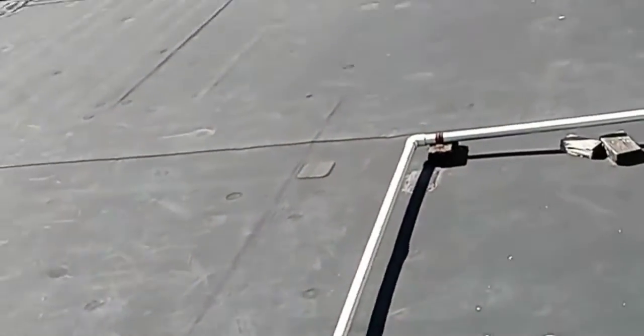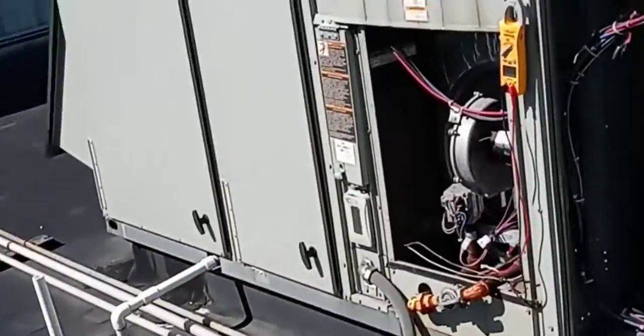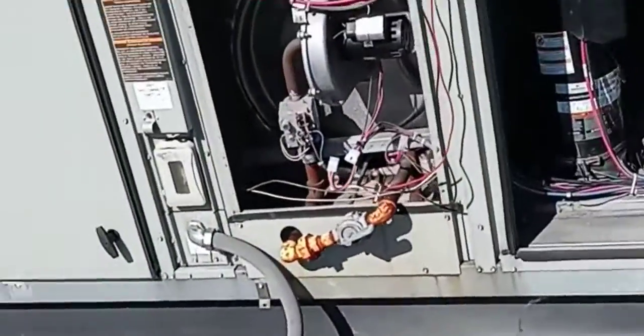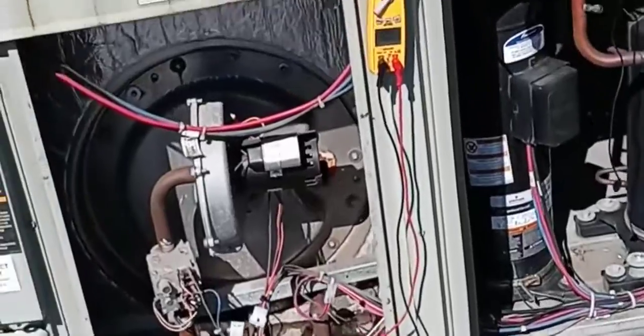I removed this panel so I can inspect the heat exchanger. If you see any cracks or any holes or any rusted out cracks on the heat exchangers, you guys want to recommend to get those heat exchangers changed out while the weather is still nice. Because you don't want to be changing the heat exchanger in the middle of the winter. So that checked out good. I came over here.